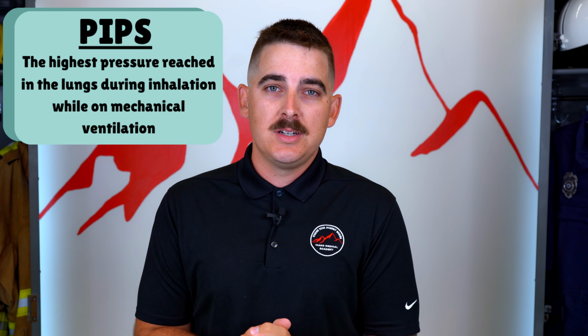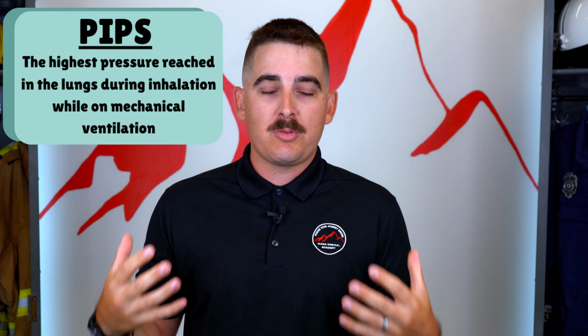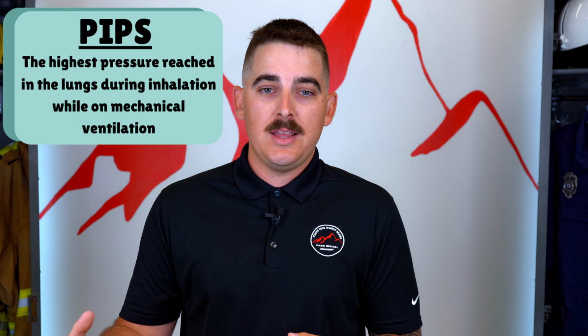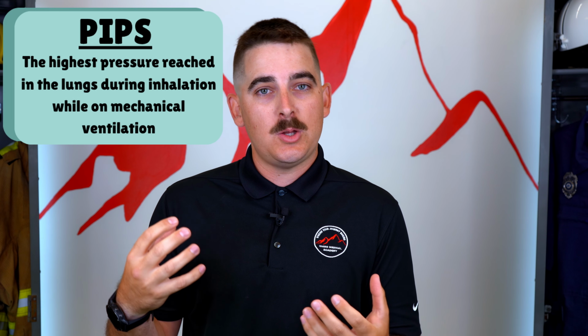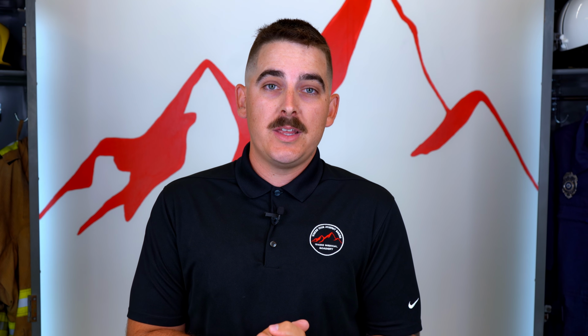Another term we need to utilize is peak inspiratory pressure, and that's going to be the maximum pressure that is delivered into a closed system. That's basically the pressure against our lungs and our alveoli when we take that breath in. Really, the maximum pressure we want to utilize is anything below 30 centimeters of water. That's going to be kind of our maximum safe peak inspiratory pressure.